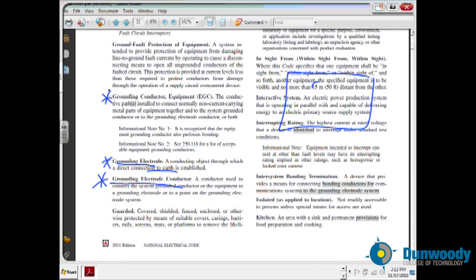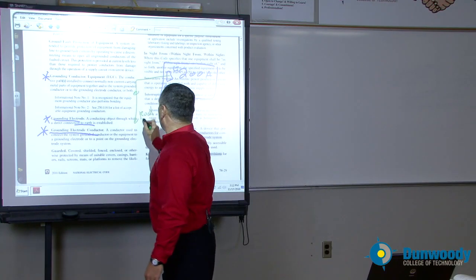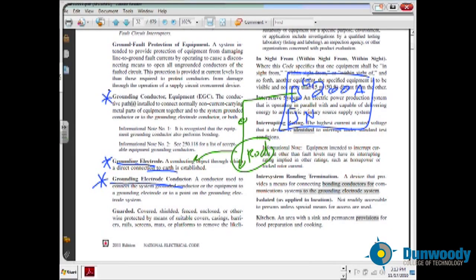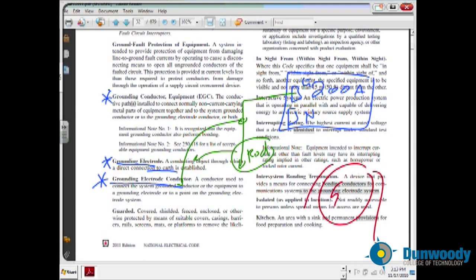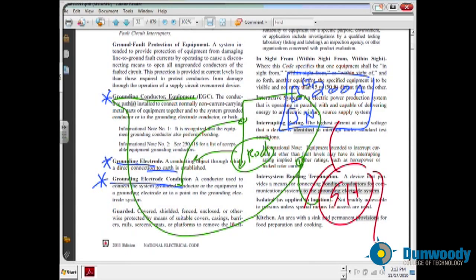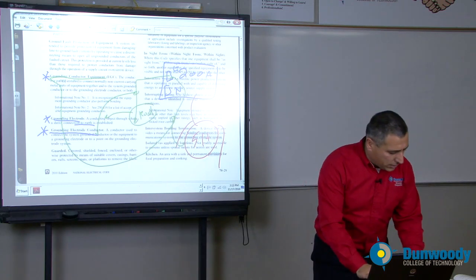So if I have a 200 amp panel: this is my neutral, this is my ground, and I take from the ground directly to Mother Earth — to a rod. That conductor going to the rod is my grounding electrode conductor. The rod itself is my grounding electrode. And if I have a machine — say a five horsepower motor fan connected to the system — the conductor grounding that fan is called the equipment grounding conductor. Three different unique terminologies we use with grounding.